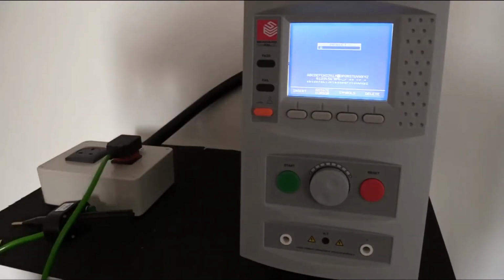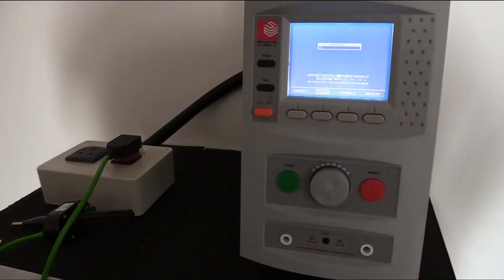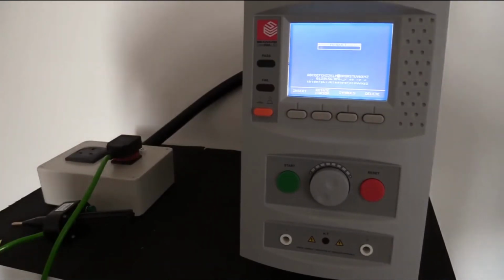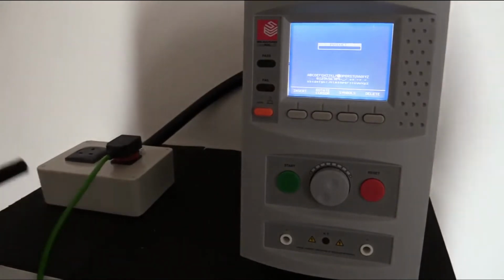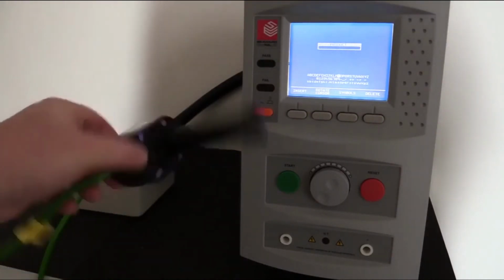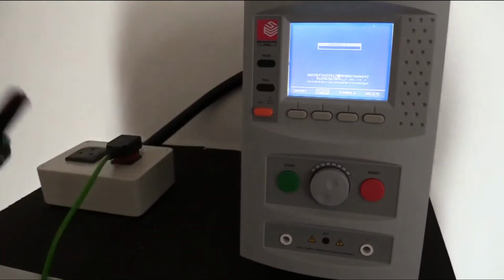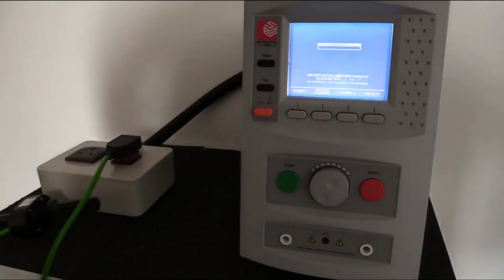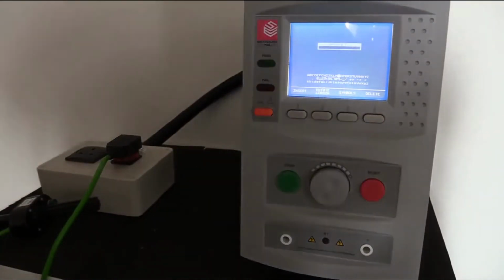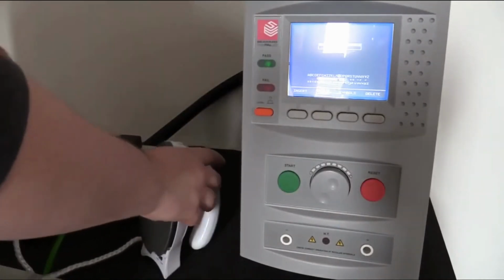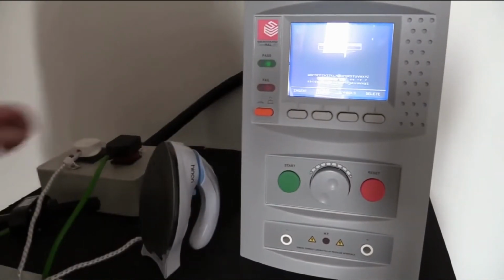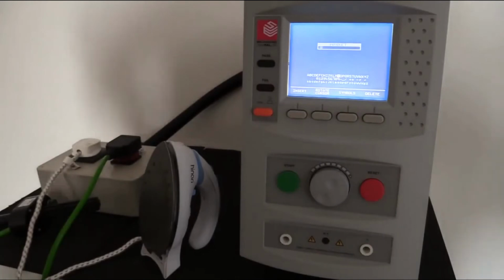Okay, so we've created our test sequence. We can now go ahead and perform that test sequence. In order to show you and demonstrate the test procedure, for this particular demonstration we're going to need our earth probe and we need something to test. For today's demonstration we're going to use a small travel iron. The unit is a class 1, meaning it has an earth.